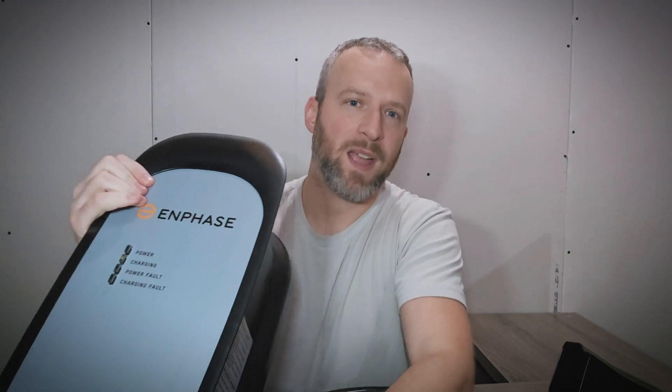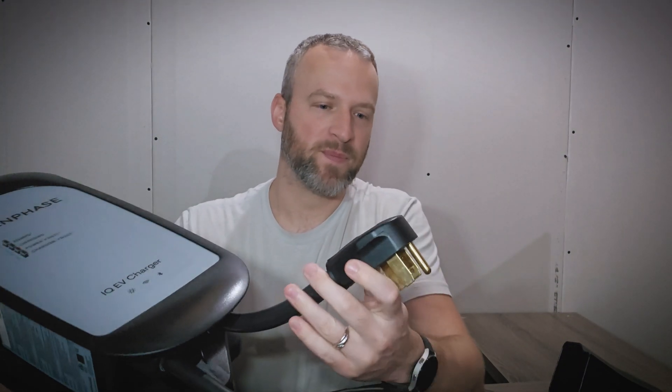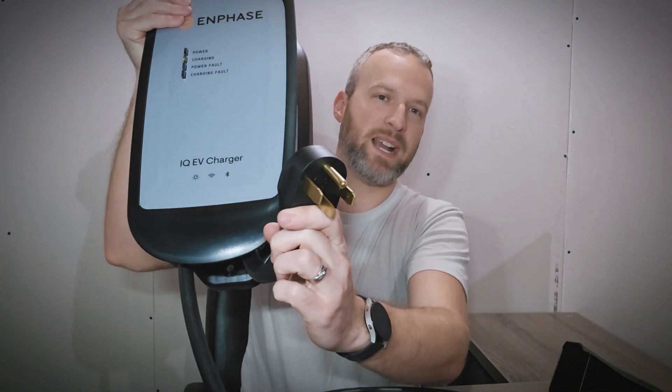It is a very high quality unit. It's quite large, with an integrated design where you can hang the cables over top of it. It does have a very short input cable, which I'm not the biggest fan of. The 14-50 connector looks good, but you don't have a lot of room to play with, and it's actually oriented upside down from most chargers, so you'll want to make sure the outlet is put in the correct location. They do include a Hubbell NEMA 14-50 outlet with your charger, which is pretty nice — these are not cheap and are some of the best quality you can get.